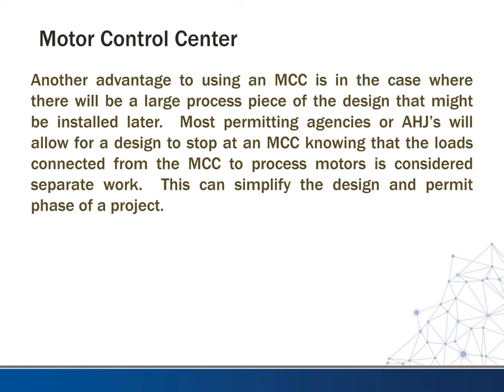Another advantage to using the MCC is in the case where there will be a large process piece of the design that might be installed later. Again, as I mentioned, for most permitting agencies, the AHJ will allow a design to stop at an MCC, knowing that the loads connected from here to the process motors are considered separate work. So this can again simplify the design and the permitting phase of a project.